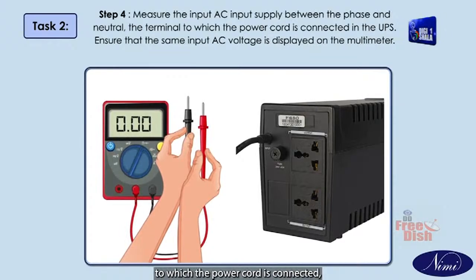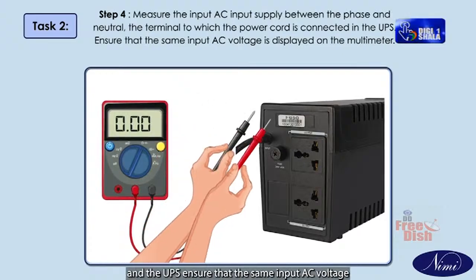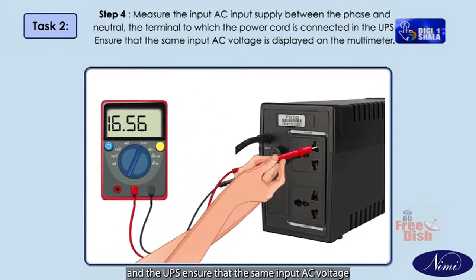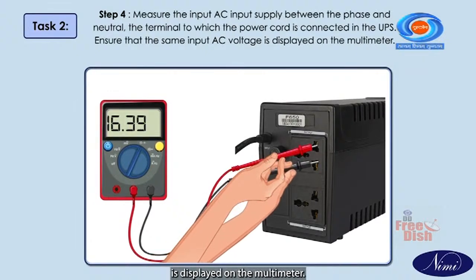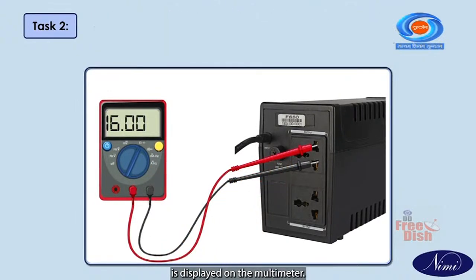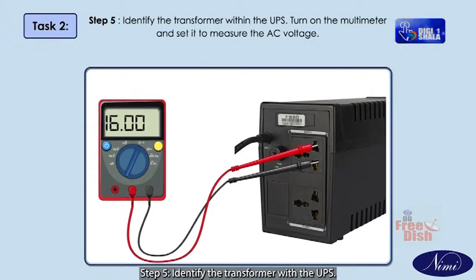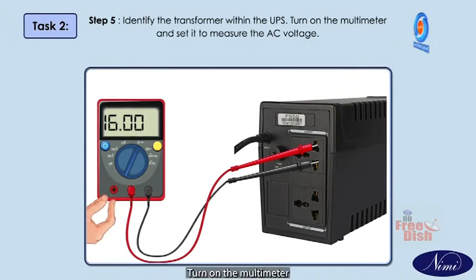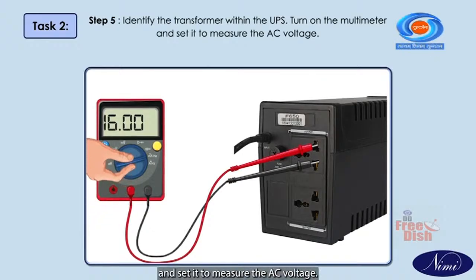The terminal to which the power cord is connected in the UPS. Ensure that the same input AC voltage is displayed on the multimeter. Step 5. Identify the transformer within the UPS. Turn on the multimeter and set it to measure the AC voltage.